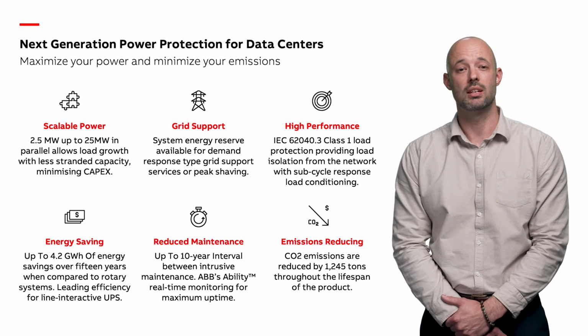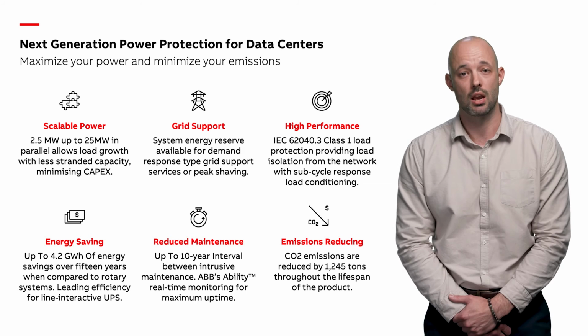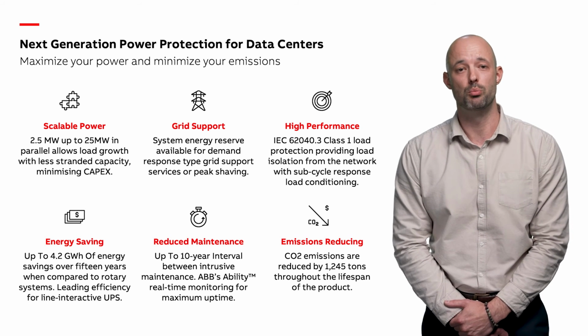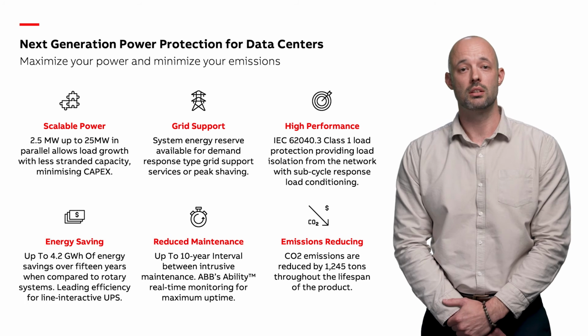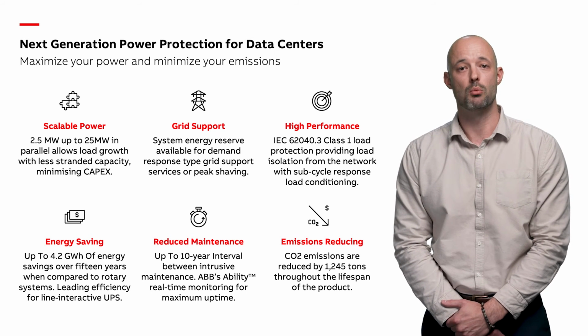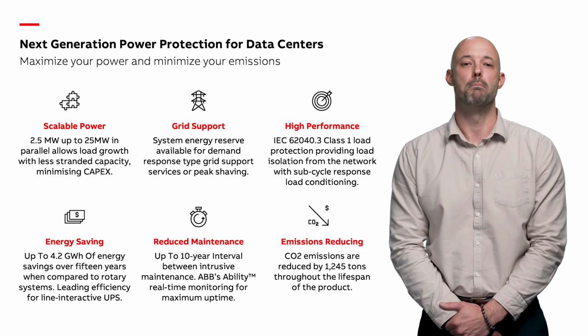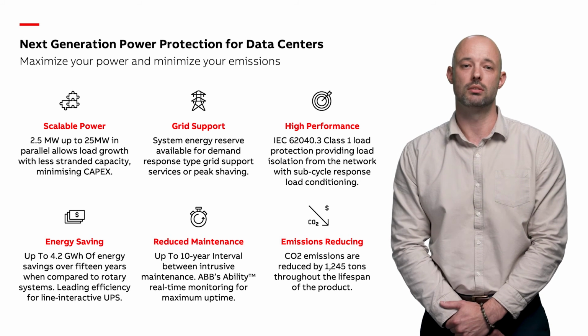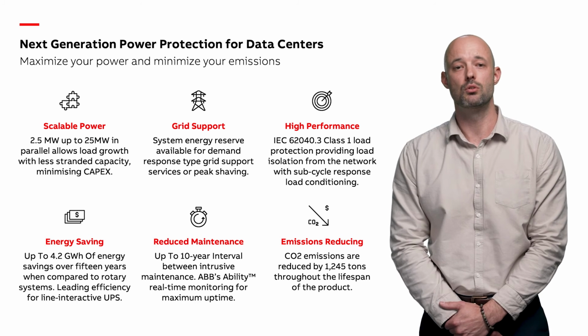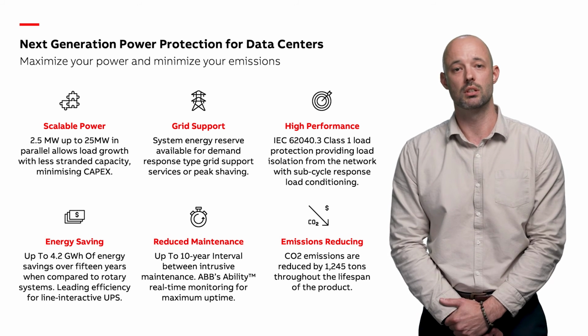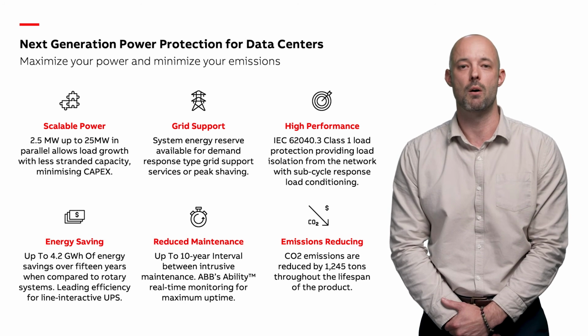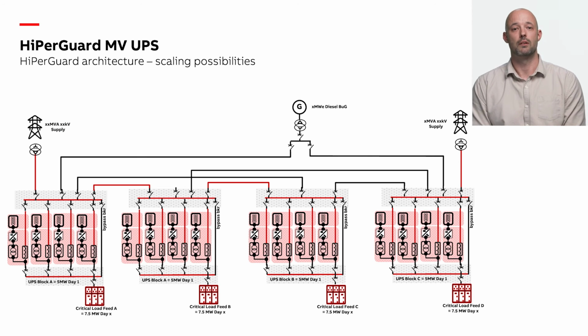Throughout this webinar, our team have identified important performance power characteristics of the HiPerGuard MV UPS. Whether utilising a single 2.5 MVA power block for an industrial load or building out multiple power trains for a large multi-megawatt data centre facility, the HiPerGuard MV UPS truly is the backbone to securing facility-wide power stability and uninterruptible power. This graphic demonstrates a 4-to-make-3 distributed redundant system protecting a load of 30 megawatt with the usage of 16 2.5 megawatt medium voltage UPS systems.